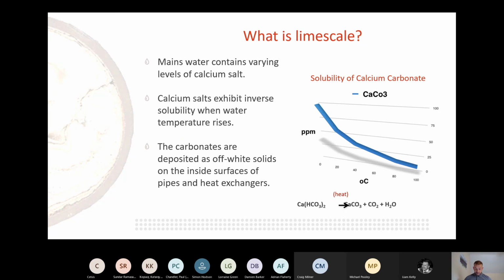Precipitation of calcium carbonate occurs at approximately 35 to 40 degrees C, and progressively worsens as temperature rises. Carbonates are deposited as off-white solids on the inside surfaces of pipes and heat exchangers. More commonly, you'll see it in the bottom of domestic kettles, to give you some visualization of what you're looking for.